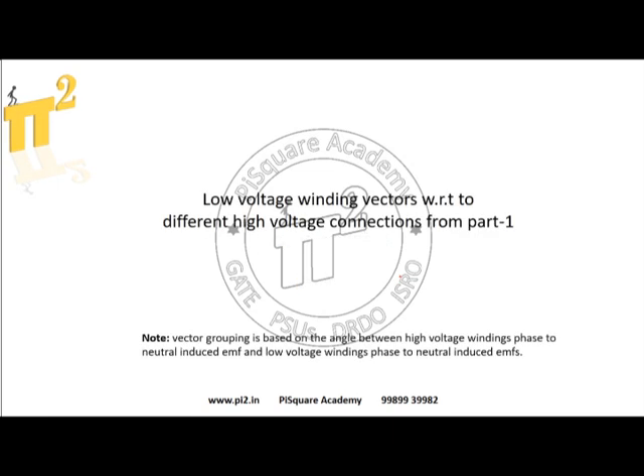Now in this lecture we will see, for those different high voltage connections, if we include the low voltage winding also, then how the phase angle will be. That is what vector grouping is — it is based on the angle between the high voltage winding's phase-to-neutral induced EMF and the low voltage winding's phase-to-neutral induced EMF.